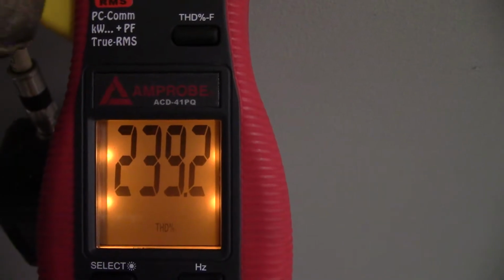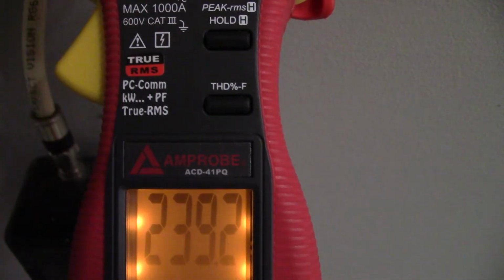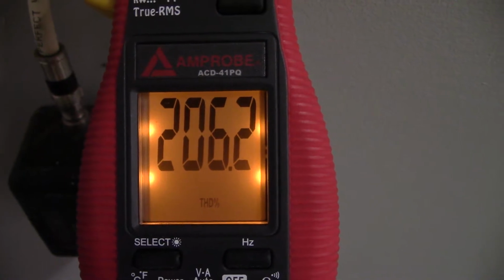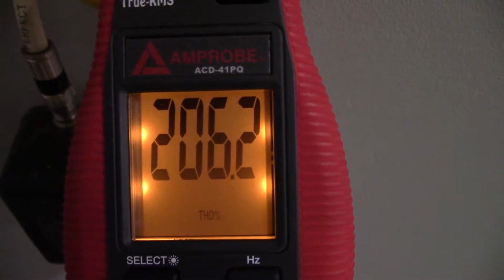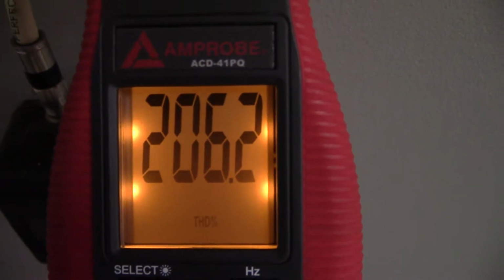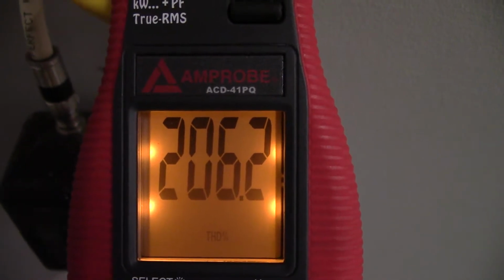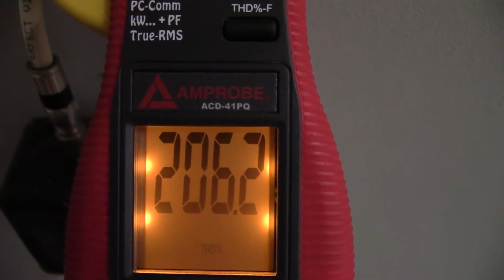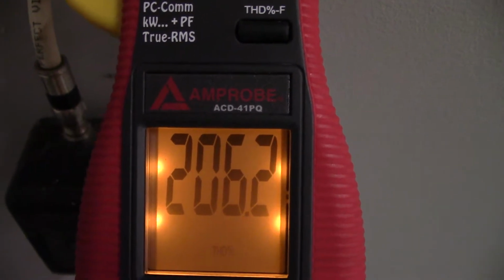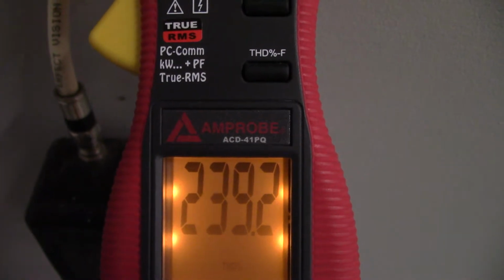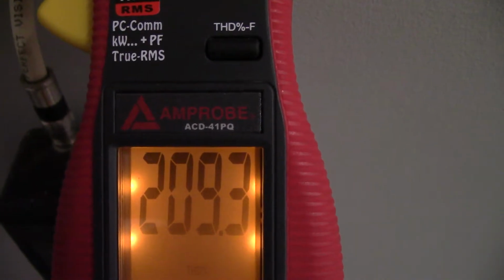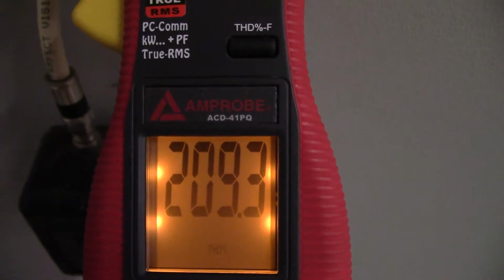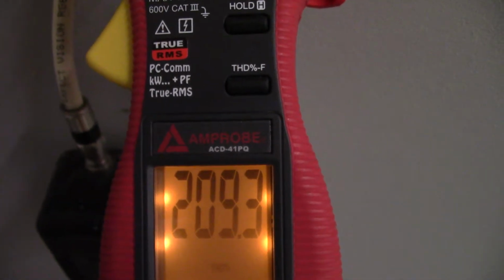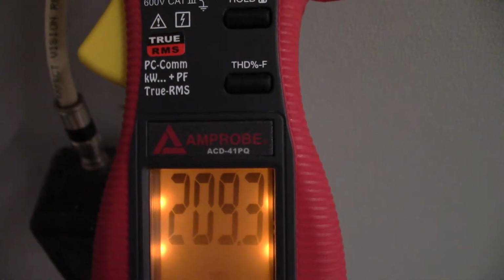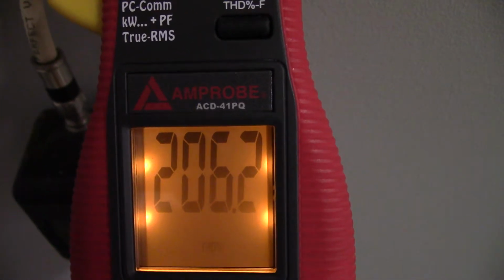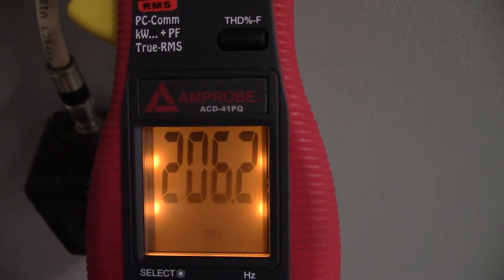I just hit the THD button. So now the primary display is only total harmonic distortion, and it's reading 206%. That's a lot of distortion. Now, it's only drawn about 0.73 amps. So the overall current that the panel is supplying through the mains, this is a very small portion of that, so the total demand distortion is very low. There's basically no voltage distortion. Okay, when your voltage distortion hits around 5%, then you know you have a problem.